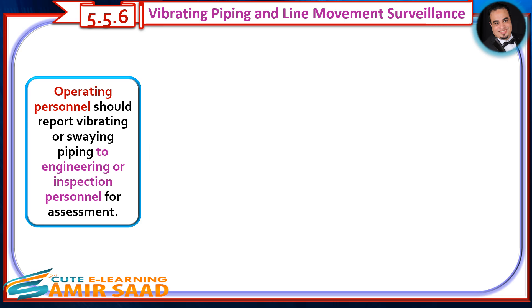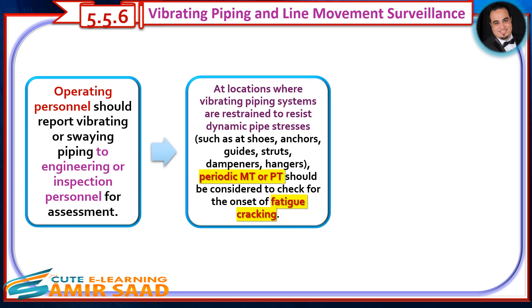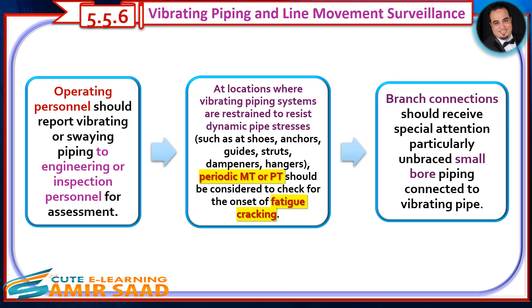Operating personnel should report vibrating or swaying piping to engineering or inspection personnel for assessment. At locations where vibrating piping systems are restrained to resist dynamic pipe stresses — such as at shoes, anchors, guides, struts, dampeners, and hangers — periodic MT or PT should be considered to check for the onset of fatigue cracking. Branch connections should receive special attention, particularly unbraced small-bore piping connected to vibrating pipe.